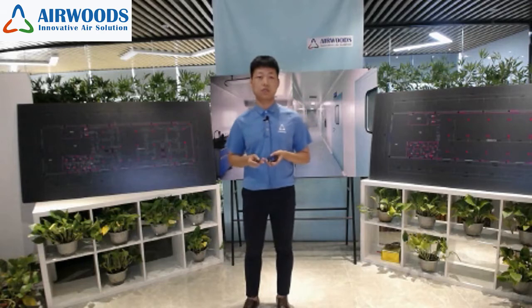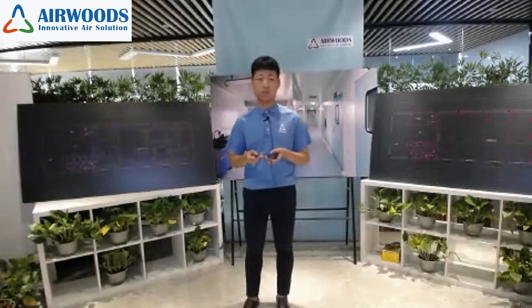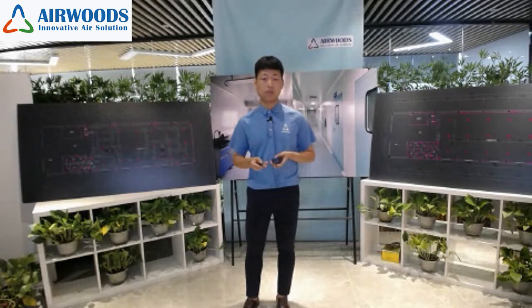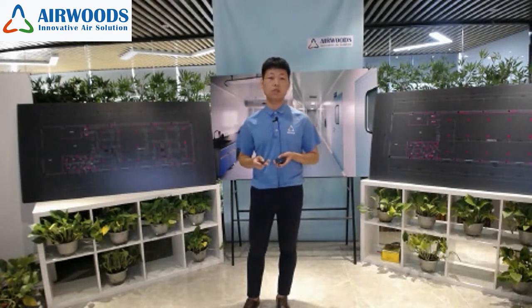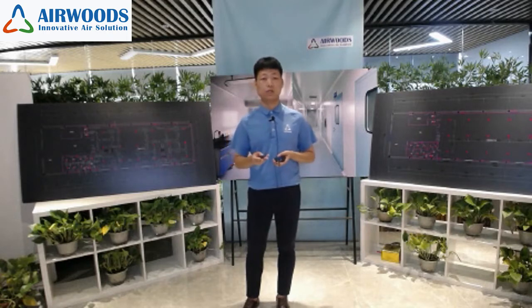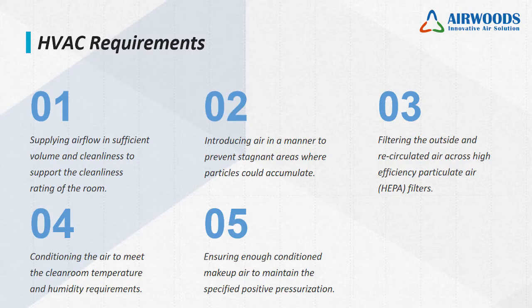Now, when it comes to the HVAC system, there are some requirements of the HVAC system design. The first one, we know the integrity of the clean room environment is created by the pressure difference compared with the adjacent areas through the heating, ventilation, and air conditioning system, right? The HVAC system requirements include 6 parts, okay? The first one is supplying airflow in sufficient volume and cleanness to support the cleanness rating of the room.